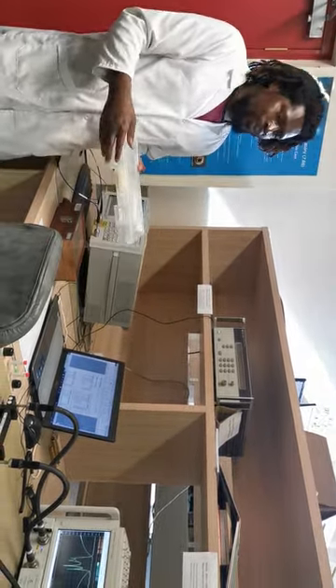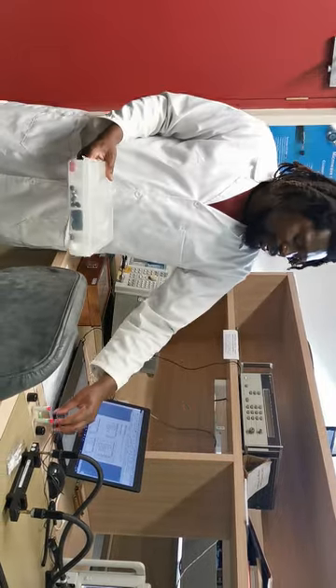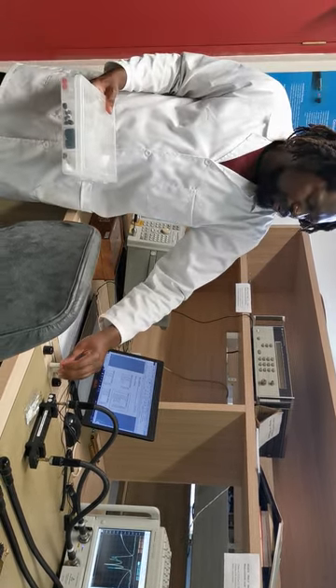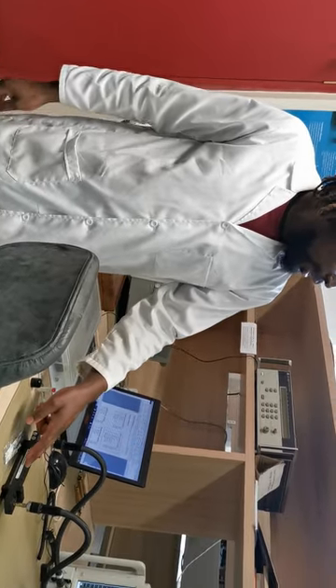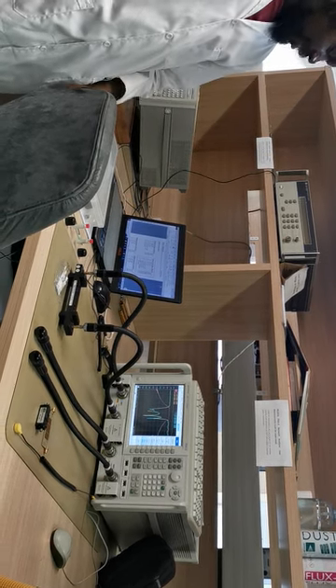Once the calibration process is complete, you're ready to do your measurement. There's a whole procedure for the calibration process itself. This accessory box contains various connectors and adapters needed for measurement. I used two male-to-male SMA adapters for this particular cable type. After completing calibration, I've now connected what I think is an X-band filter. The SMA connector refers to a specific cable type — SMP would be a smaller version of SMA.